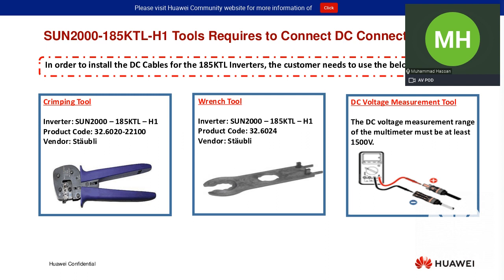So you need to purchase the Stäubli MC4 crimping tool. Make sure you use the correct one, because the MC4 crimping tool comes in different dies, so you need to use the correct product code. For the 185 KTL, the connectors we use are compatible only with the product code mentioned here, 32602 2210. If you don't use the correct die, there will be a problem with the crimping of the pins, which can cause problems later when the inverter is running at the maximum output.